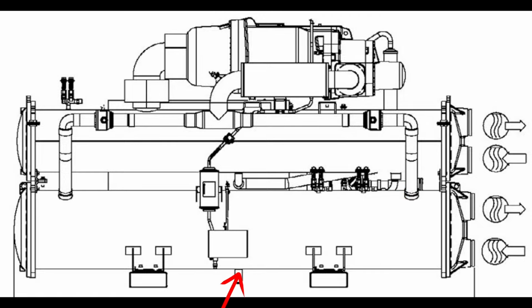Our liquid line is here at the bottom. We can see that drop leg there. This just helps create the circulation turbulence internally here, so we have an efficient condensing process. And this machine doesn't have an oil separator, right? We'll get into it, we have an eductor instead. That's what this is right here. So we have an eductor system that is acting as our oil separator in this process.